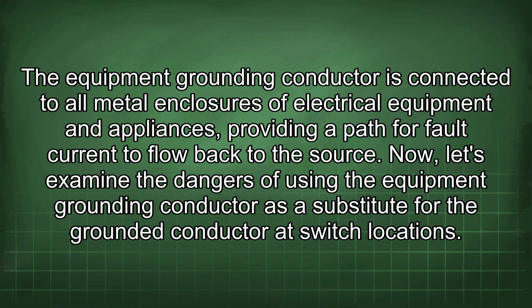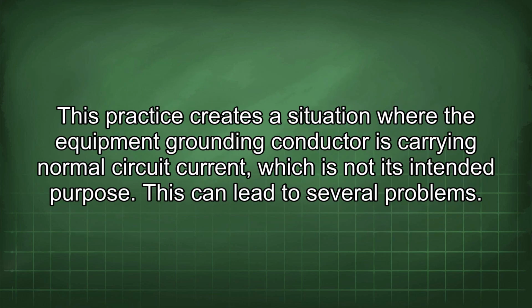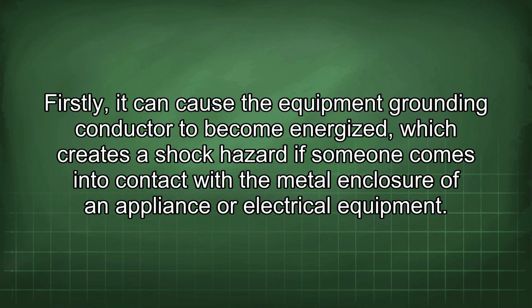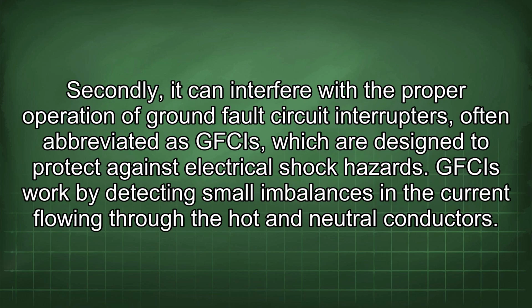Now, let's examine the dangers of using the equipment grounding conductor as a substitute for the grounded conductor at switch locations. This practice creates a situation where the equipment grounding conductor is carrying normal circuit current, which is not its intended purpose. This can lead to several problems. Firstly, it can cause the equipment grounding conductor to become energized, which creates a shock hazard if someone comes into contact with the metal enclosure of an appliance or electrical equipment. Secondly, it can interfere with the proper operation of ground fault circuit interrupters, often abbreviated as GFCIs, which are designed to protect against electrical shock hazards.